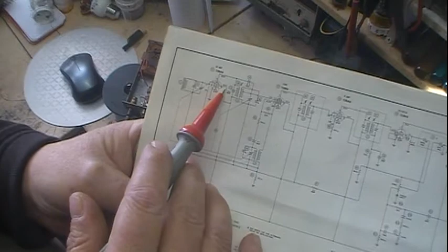They're easy enough to find, just rotate this a little bit. You can count them off at pin 1, 2, 3, 4, and 5. If you can see the meter, we get 95 or 94.2 volts, close enough to 95. And pin 6, the next pin over, is right on 95, 95.1, 95.0. It's flipping back and forth between the two. That's the screen. Now we have a couple other voltages on there.